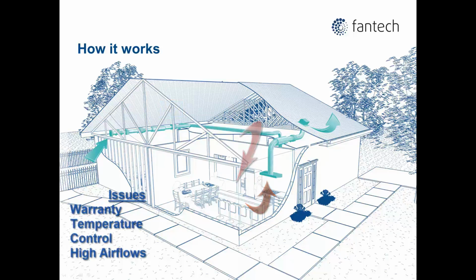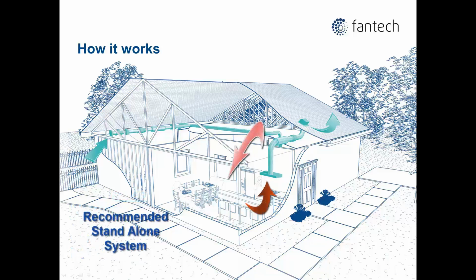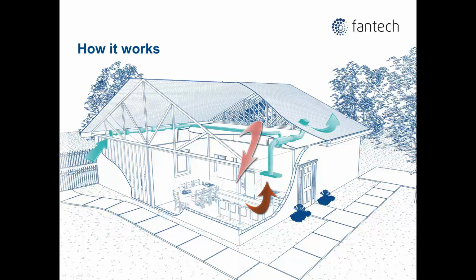Introduction of make-up air into the central HVAC system raises issues with furnace warranty, temperature control, and the central system's ability to handle a high percentage of outdoor air. For these and other reasons, it is strongly recommended that the make-up air system not be integrated with the central HVAC system. When a make-up air system includes tempering, a filter is required per ASHRAE 62.2. However, it's good practice regardless. A filter helps to remove outdoor dust, pollen, etc. and stop it from entering the home.